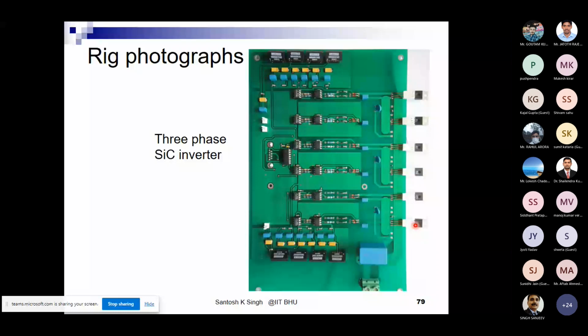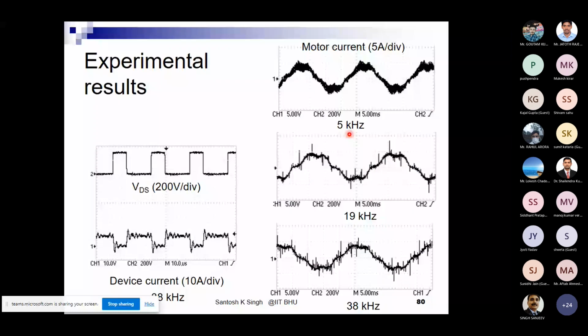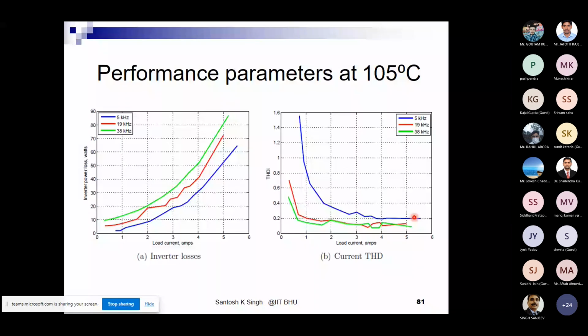These were a few of the experimental results as a function of switching frequency. You can see that if you increase the switching frequency, certainly you get some improvement in the nature of these ripple currents. But if you jump from 19 to 38 kilohertz, there isn't much difference reflected. So in motor drive application, it's okay to go up to 20 kilohertz, you don't need to take it to a very high switching frequency. For boost converters, certainly that is required, but not for inverters.